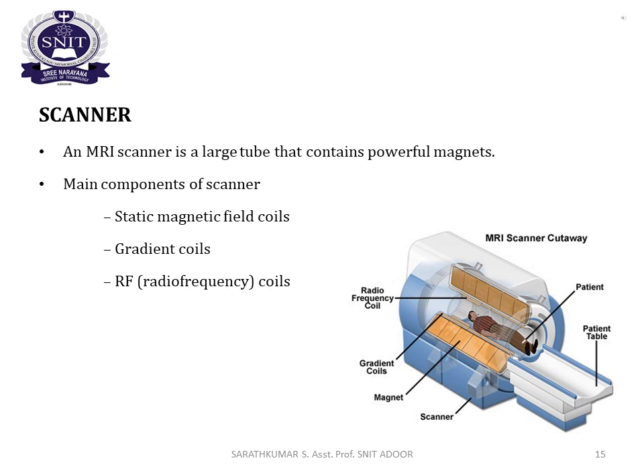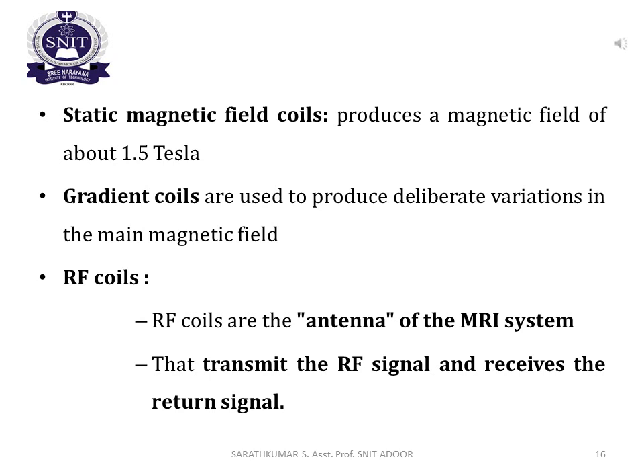The main components of the MRI scanner are: static magnetic field coil, gradient coil, and radio frequency coil. The static magnetic field coil produces a magnetic field of about 1.5 tesla. Gradient coils are used to produce deliberate variations in the main magnetic field. Radio frequency coils are the antenna of the MRI system that transmit radio frequency signals and receive the return signals.